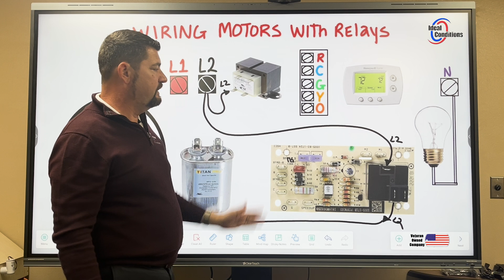Okay, I'm going to come over here. I'm going to give my run winding a leg of power. Go ahead and label that. I'm going to give my start winding from my run capacitor a leg of power. I'm going to come out, land that on start, and as long as my capacitor is closed, as long as it's not open or shorted, then L1 will be present all the way through. And with this, my motor will be good to go.